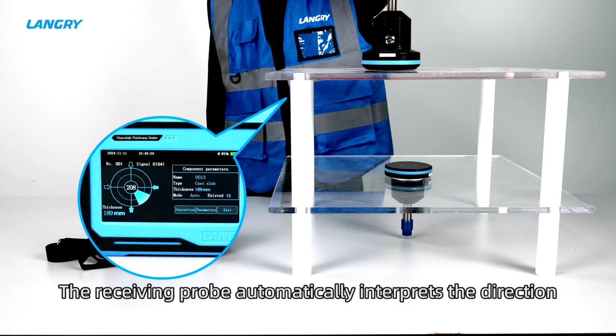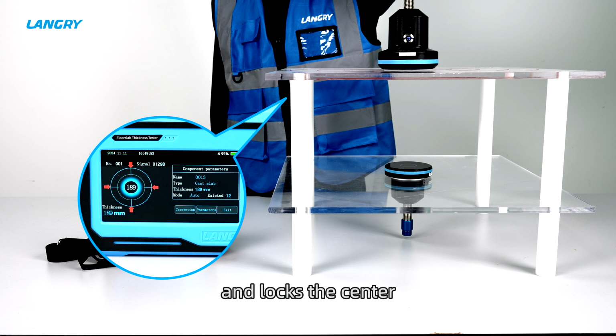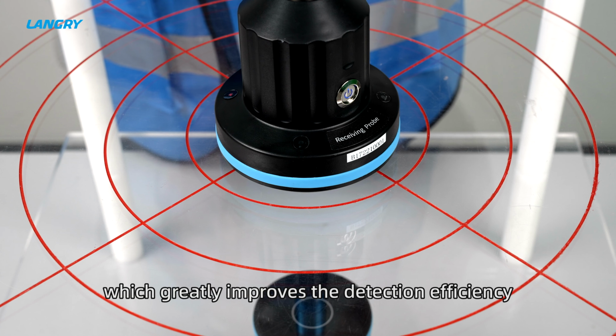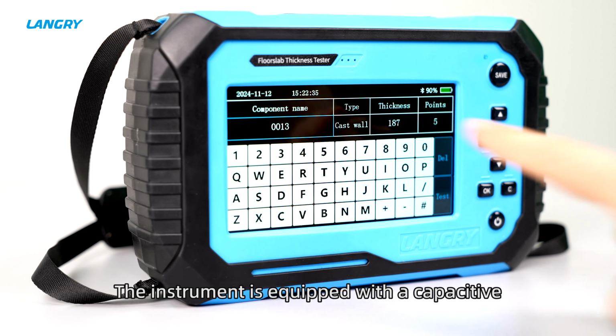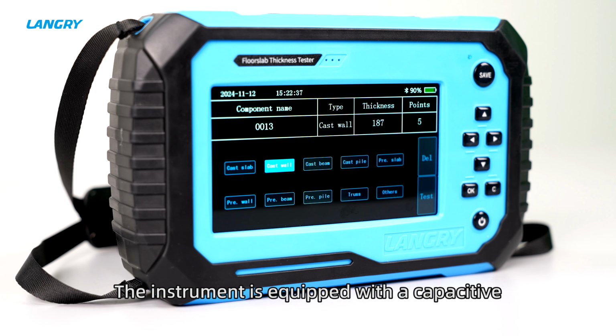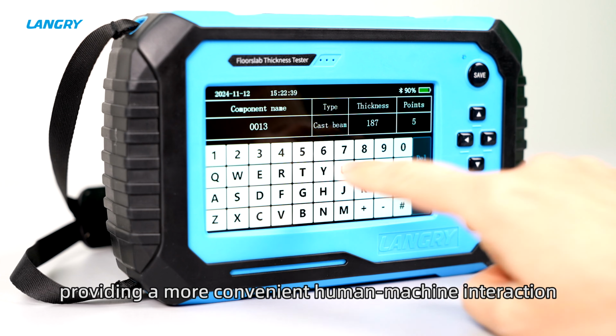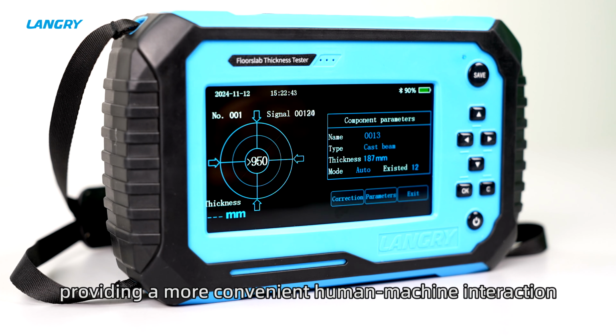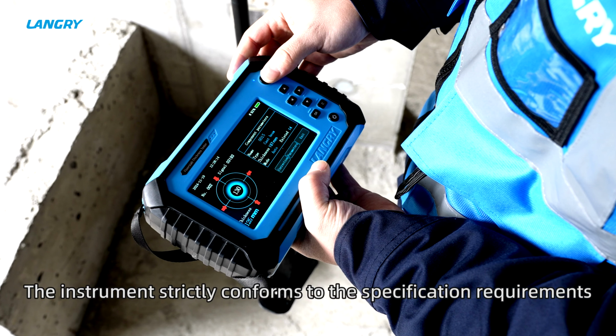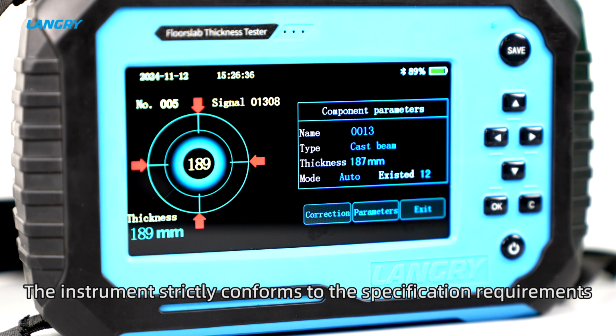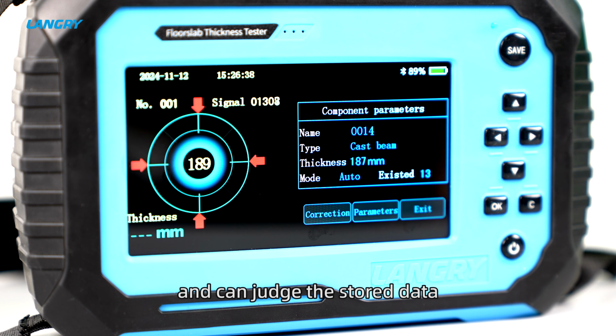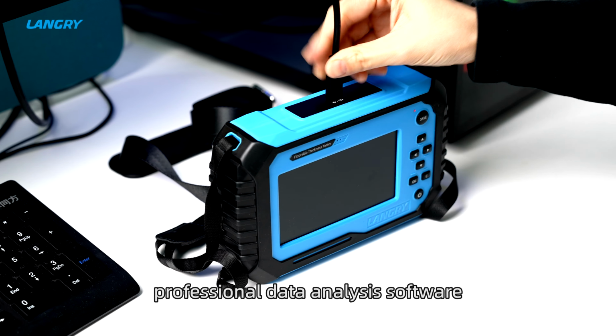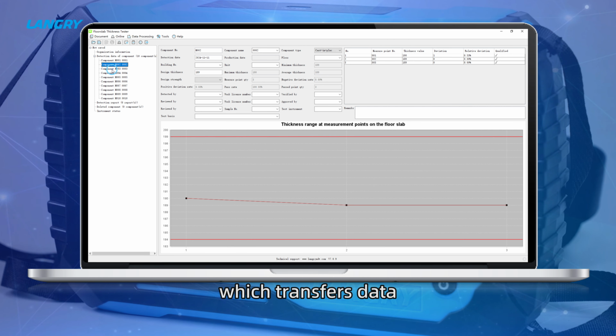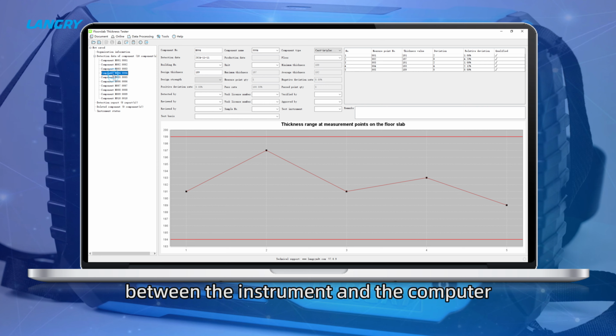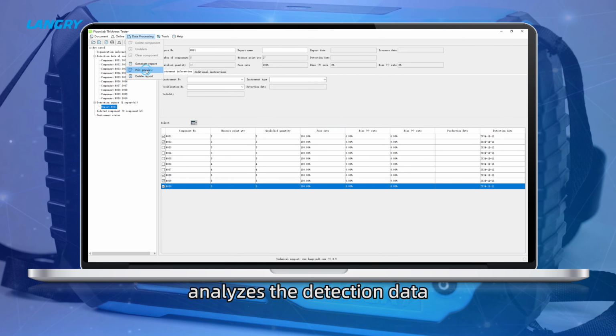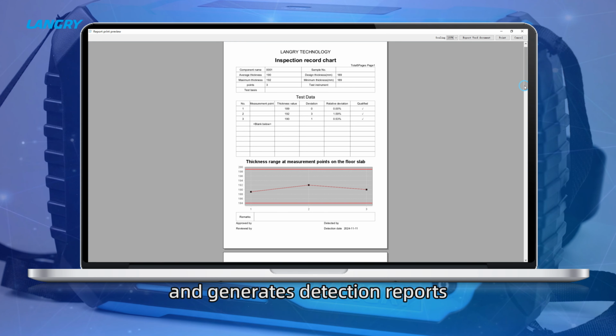The receiving probe automatically interprets the direction and locks the center, which greatly improves the detection efficiency. The instrument is equipped with a capacitive touch screen for full touch operation, providing a more convenient human-machine interaction. The instrument strictly conforms to the specification requirements and can judge the stored data. The instrument is equipped with professional data analysis software, which transfers data between the instrument and the computer, analyzes the detection data, and generates detection reports.